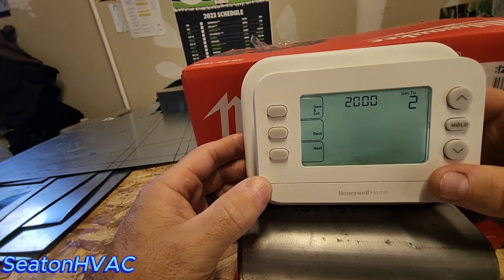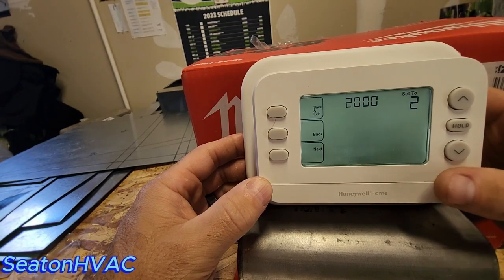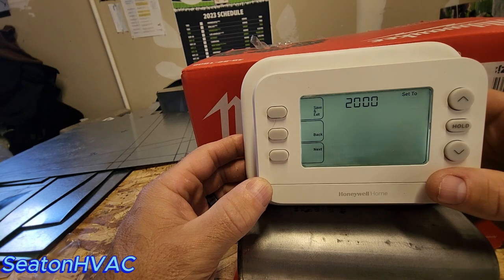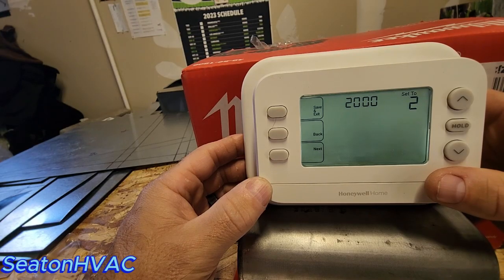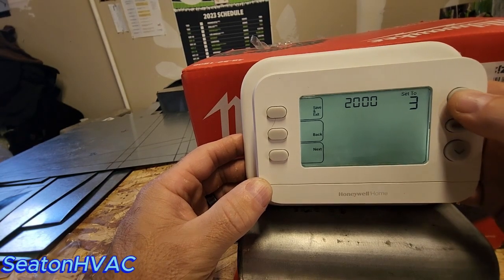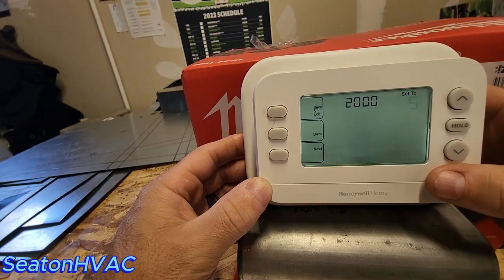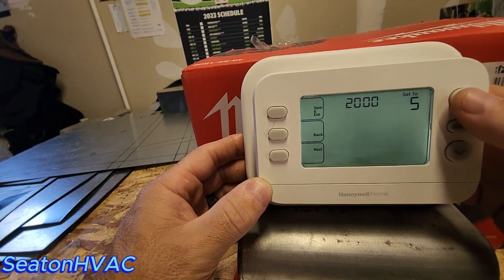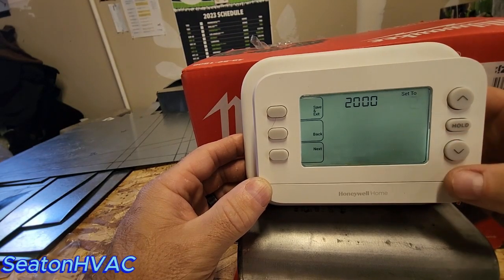And then 2000 would be your heating system type. 1 is conventional forced air heat, if it was a gas furnace. 2 is a heat pump. 3 is radiant heat. Like I said, this one's been programmed, so it's going to be on what I set this one up as. I had to pull it off the wall because the customer wanted a different one. They wanted the Wi-Fi thermostat. 5 is none. That's if it's just an electric furnace, or an electric furnace that doesn't have any cooling, you'd bump that to 5. But since we have a heat pump, we'll go back to 2.